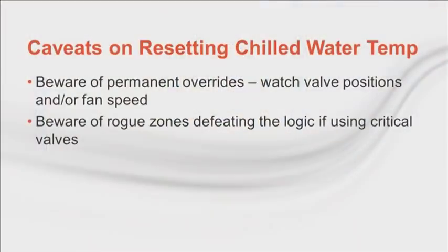As a secondary control strategy, consider chilled water reset when the flow is low enough that the chiller minimum flow bypass is being invoked. Turning the temperature up opens the valves and may avoid the need for some or all of the bypassed flow. And of course, we said it earlier, beware of permanent overrides. It is possible to have too much of a good thing. If there are some zones that just are never happy, they can defeat the logic of both strategies. Be vigilant and investigate valves that are always wide open. System differential pressure-based reset is less prone to rogue zones. The differential pressure signal will represent a more generalized view of how unloaded the building is.